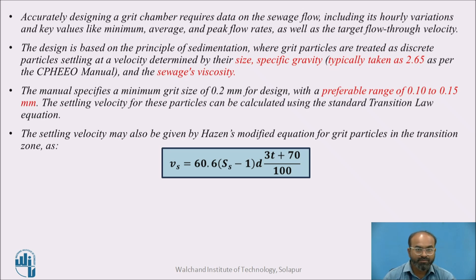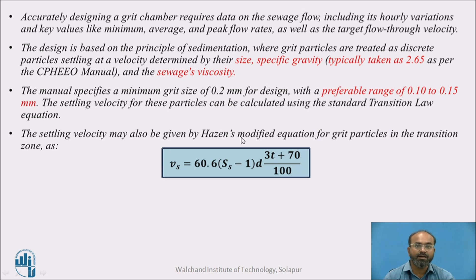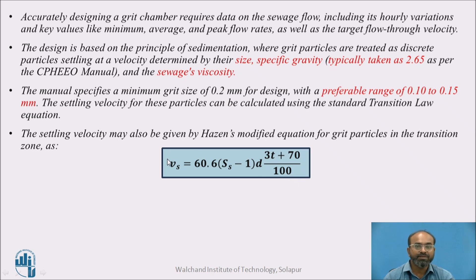Although we design the grit chamber with respect to type one, grit is not a true type one discrete particle — it shows different characteristics. So the design is done with respect to transition zone or transition flow, which can be calculated using Hazen's modified equation. That is: Vs = 60.6 × (Ss − 1) × d × (3T + 70) / 100, where Ss is specific gravity, d is diameter of grit particles in centimetres, and T is temperature of sewage, giving the settling velocity of grit particles.